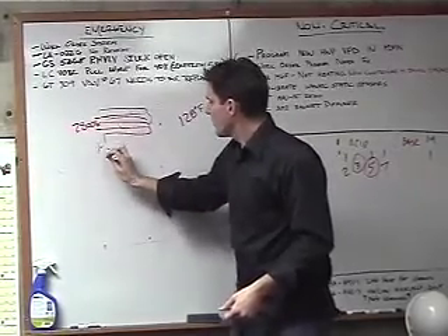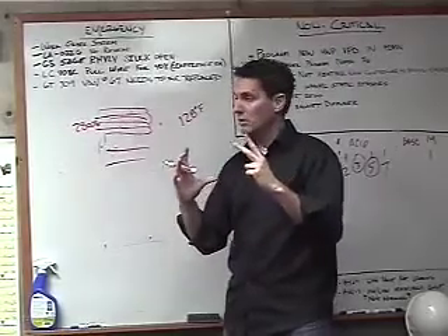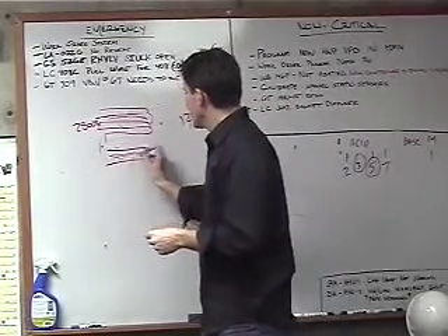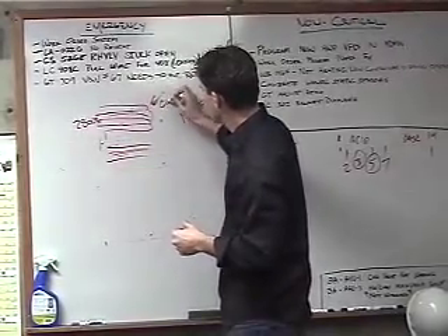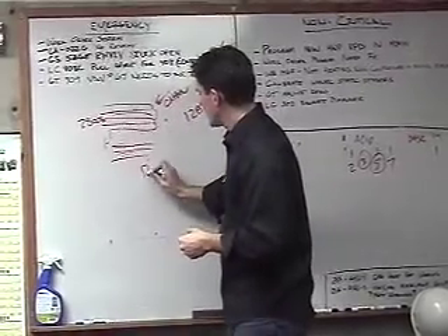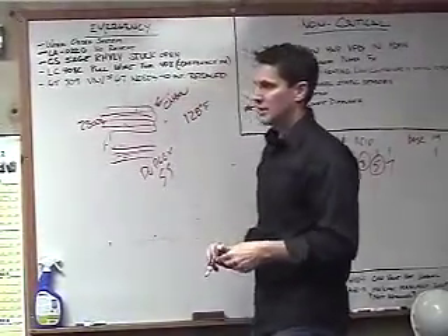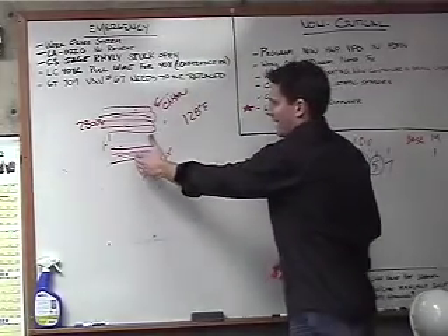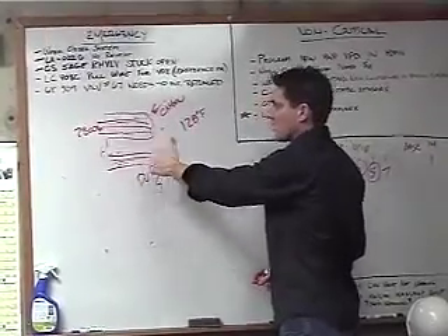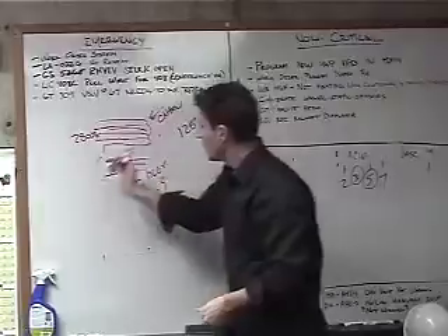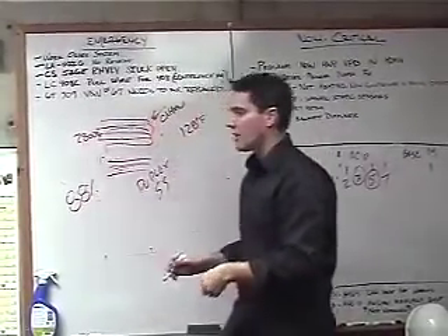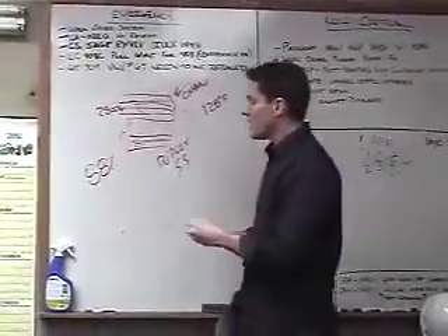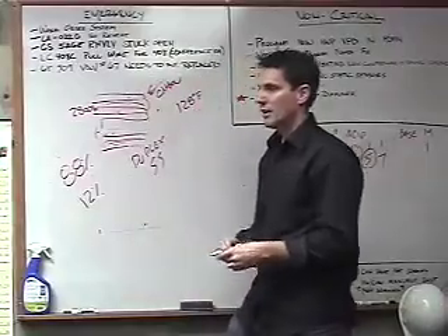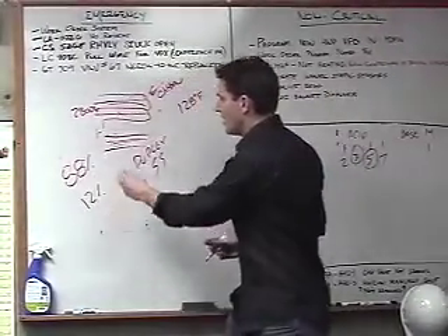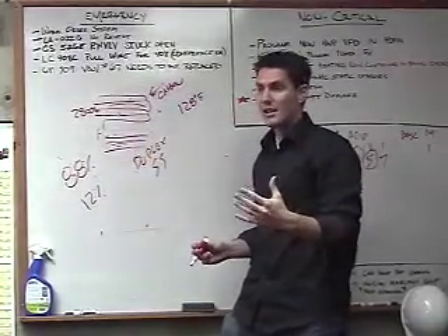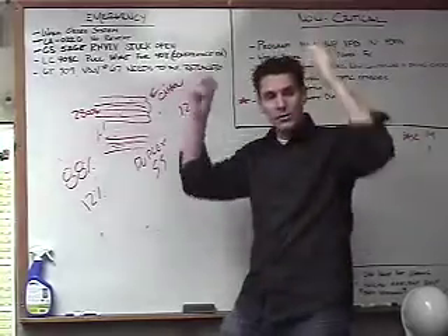So then we drop it down and we run it through another heat exchanger. This is kind of like a straight through shell and tube bundle. And this up here is made out of a heavy grade carbon steel. This down here is made out of duplex stainless steel. Some of the heaviest grade stainless that you can get. This is where we're going to condense. This is where we're capturing the rest of that 12% heat energy. Remember, before we condense, we can get 88% of the heat energy out of our natural gas mixture. But if we want to be 100% efficient, then we have to capture the last 12% of my high heat value. So in order to pull that out, that's what we're doing down here. You guys ever used economizers, stack economizers, where you grab the residual heat off of your flue that leaves the boiler?